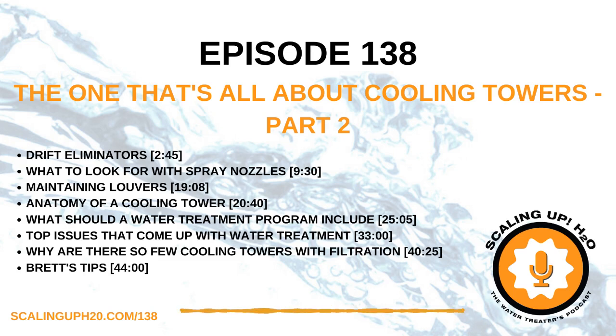I'm sure listeners immediately know what we're talking about when we mention louvers—the piece on the cooling tower that customers look at and say, hey, there's scale on these, your system isn't working. But those are evaporative salts, areas that got wet and then evaporated. So many people out there think those are scale, and I want to make sure that's clear: that's not scale.